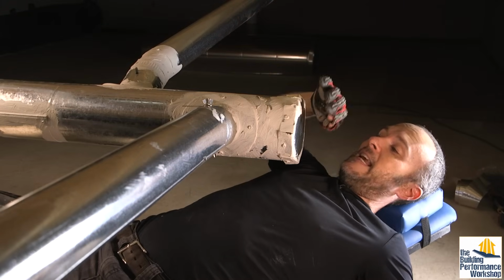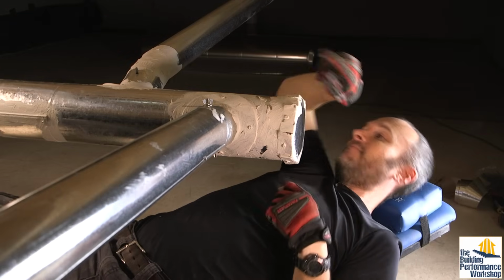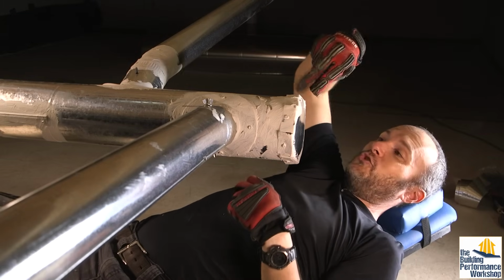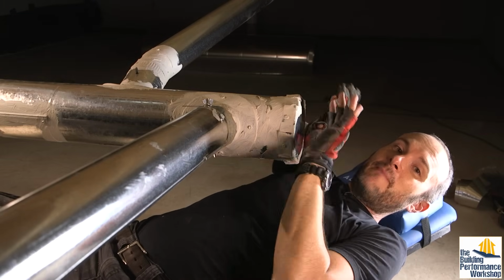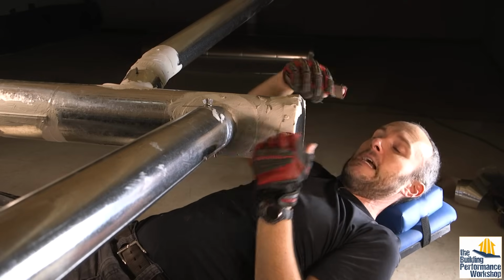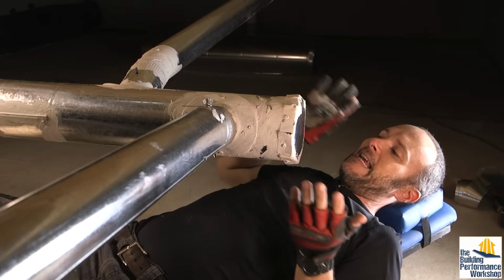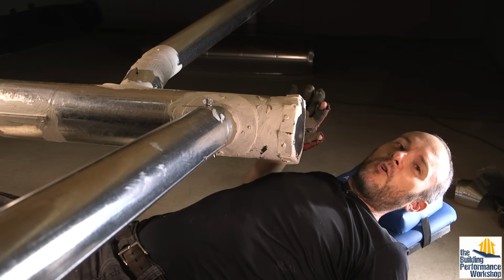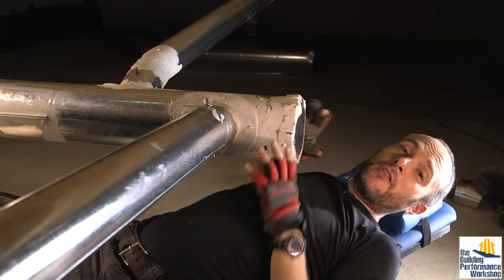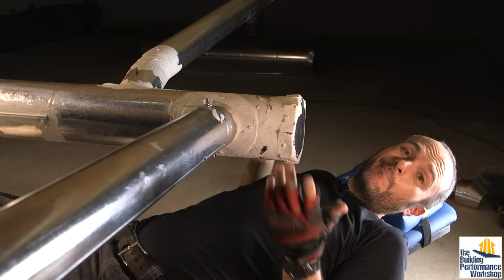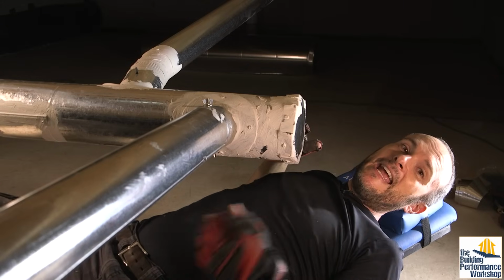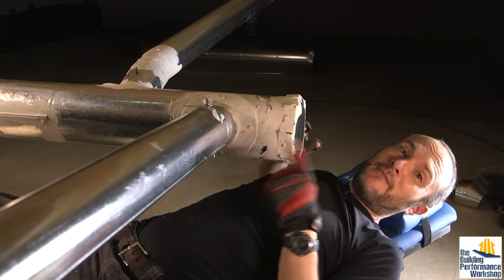Or I could just take a piece of sheet metal that's cut in a circle and then trim the edges into a flower shape and then bend each of those over and then mastic the whole thing. It takes a little more on the mastic side and a little more on the screw side and a little bit more on the time side, but is it worth it to you to go out and have to buy an extra cap that you forgot about?